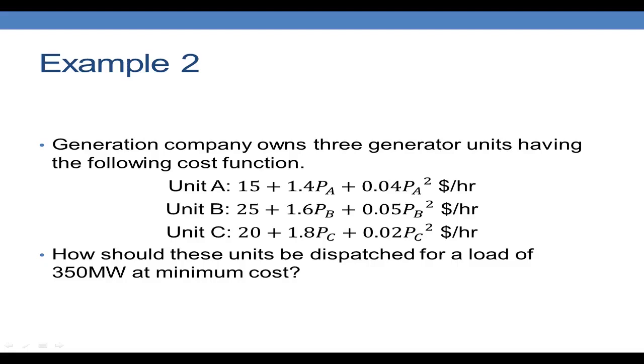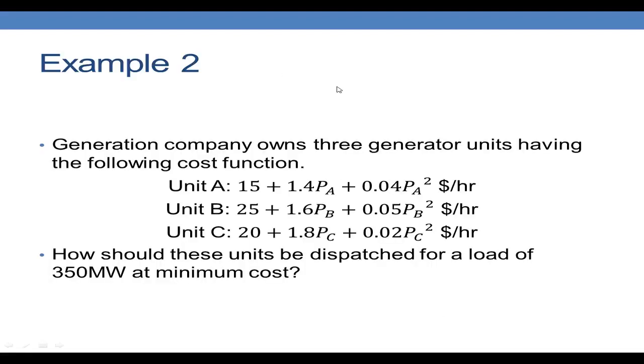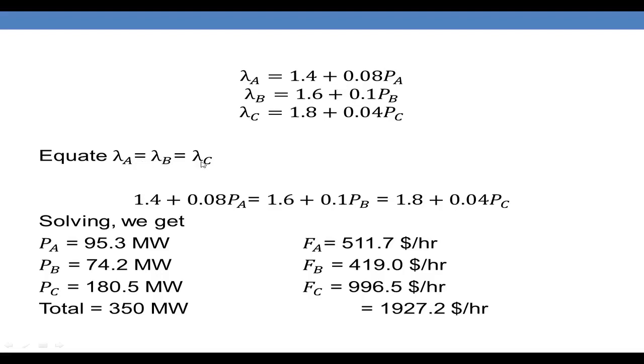I have solved this problem here. Lambda A is the first derivative of the cost equation, and we equate lambda A, lambda B, and lambda C. After equating, the power to be generated from generator A is 95.3 megawatts, PB is 74.2 megawatts, and PC is 180.5 megawatts — totaling 350 megawatts. The cost of generating 350 megawatts is 1927.2 dollars per hour, which is the minimum cost achievable.